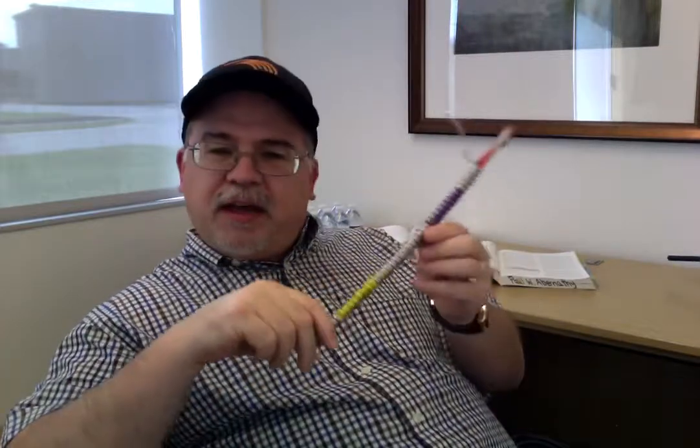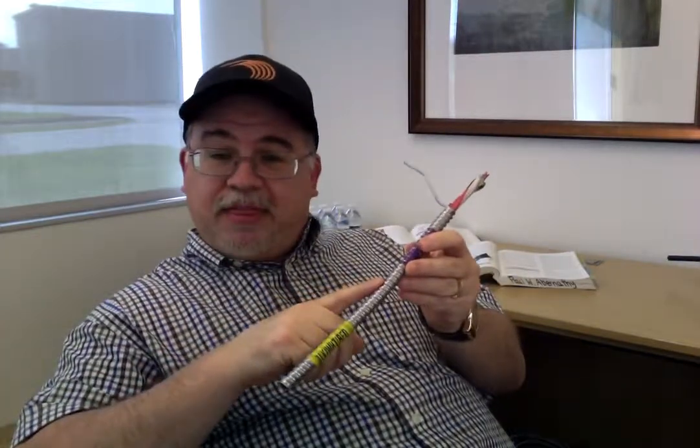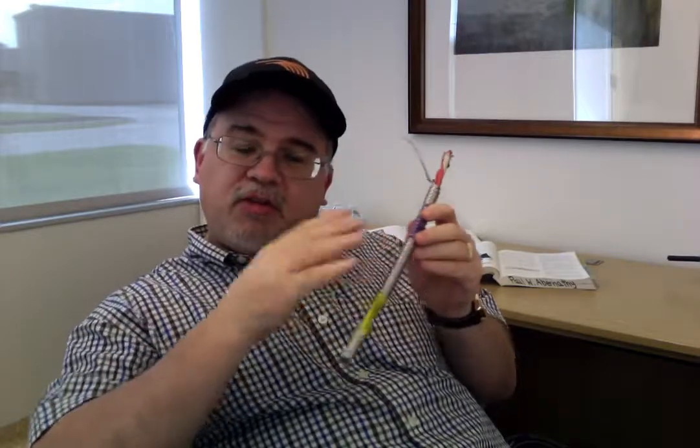UL 1569 tells us what size this has to be and what it's intended to do. But then all you need to do is look at the National Electrical Code. It'll also give you guidance when you look at 250.118 item number 10, sub-item B. That tells you that when you take a bonding/grounding conductor and you put it in contact with an armor, now it becomes an effective ground fault current path, or basically an equipment grounding conductor, as stated in 250.118. So that's what we're utilizing here. So this becomes an effective ground fault current path, because this aluminum conductor touches every convolution through the entire length of that cable assembly.